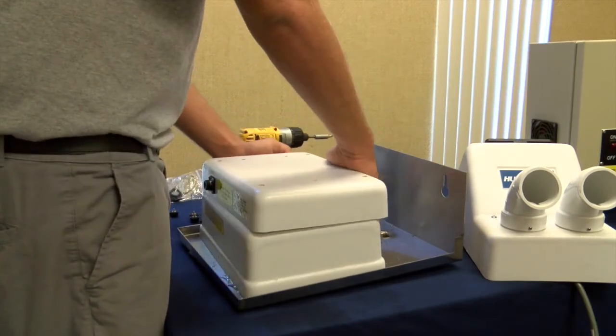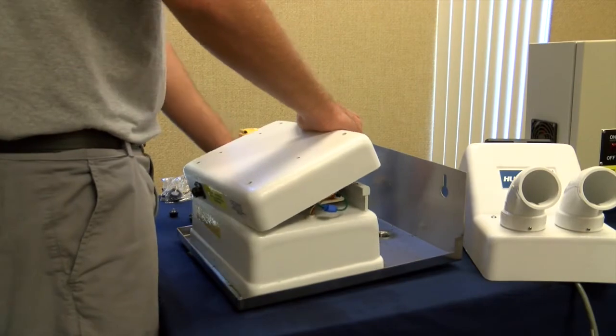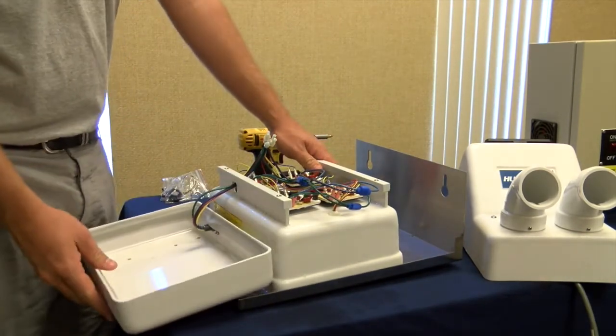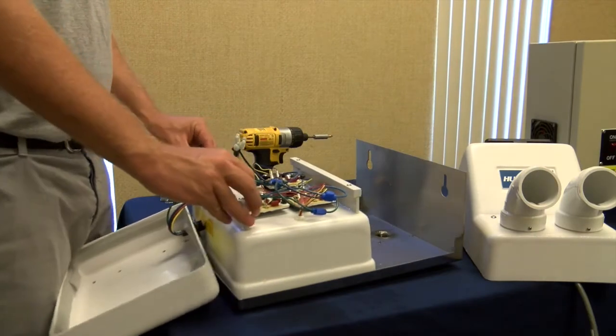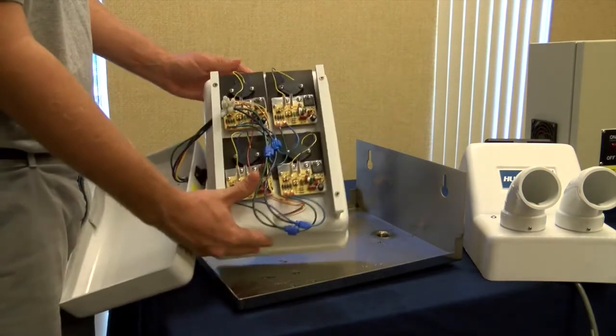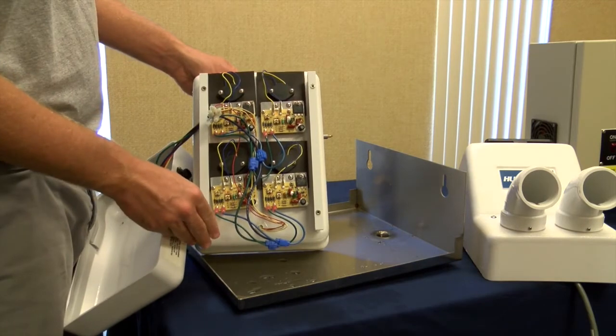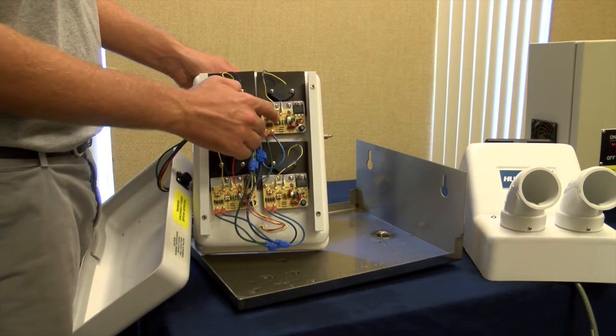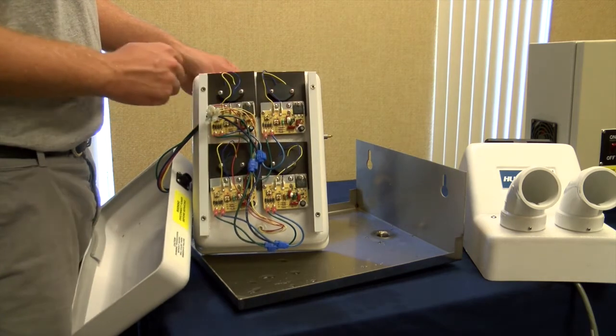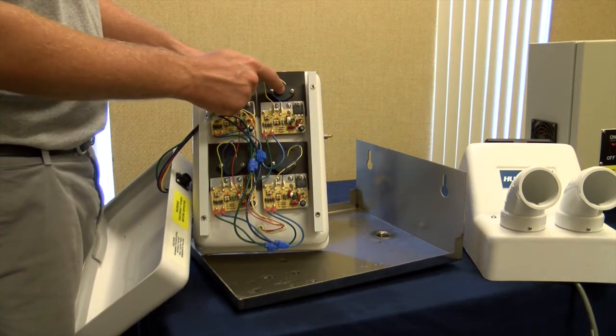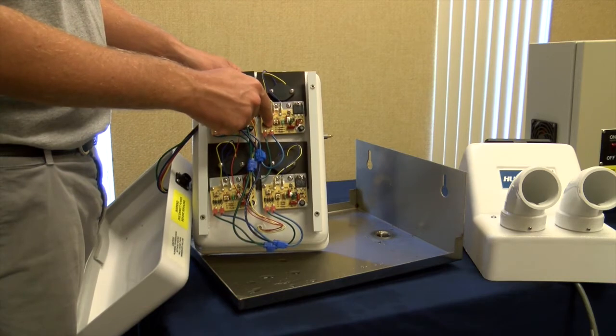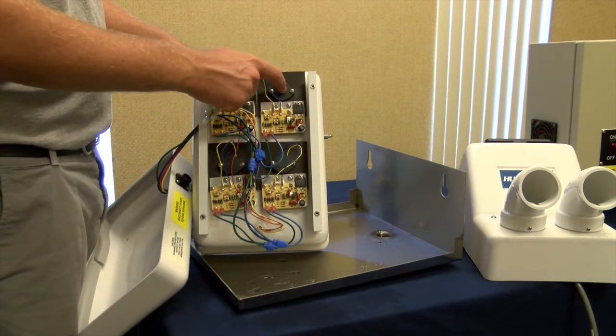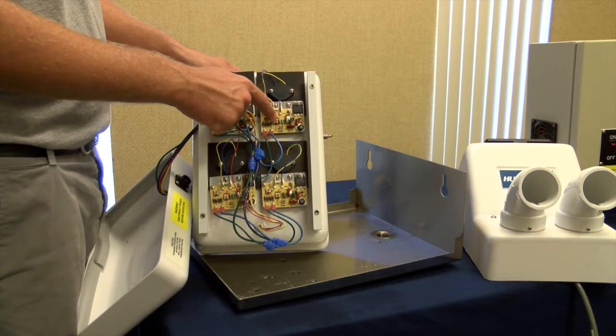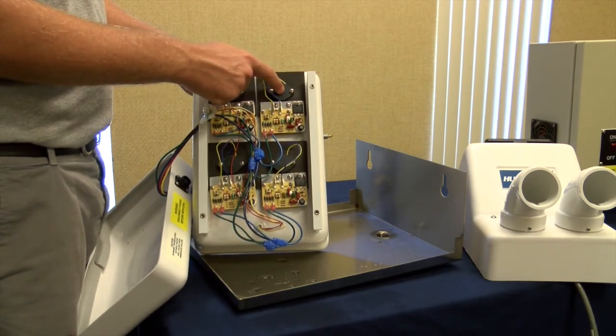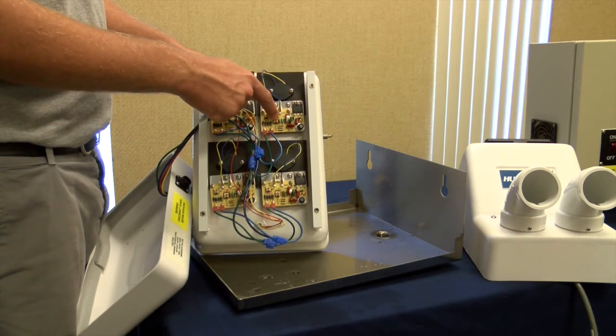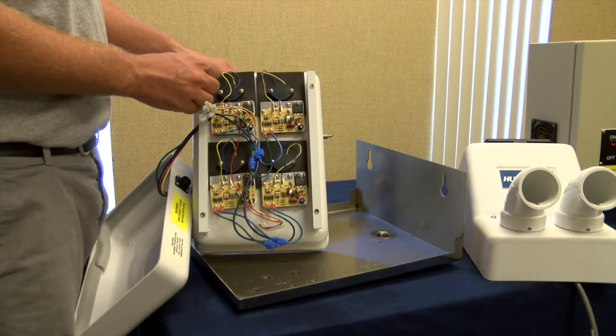Now, you're going to want to pull the unit open. Now, you will notice each of the transducers has the transducer and the print plate. When ordering new transducers, you'll get a new transducer and print plate. Be sure to change both the transducer and the print plate. If you just change the transducer and not the plate, you can then cause premature failure.